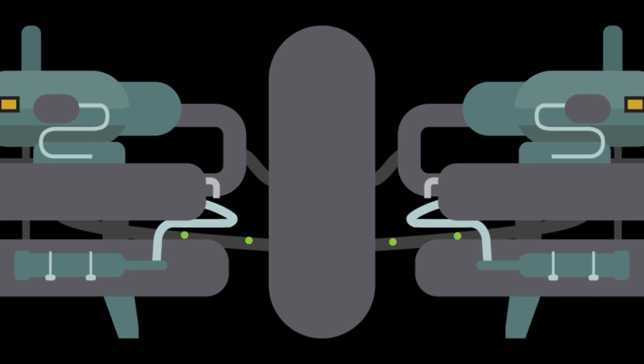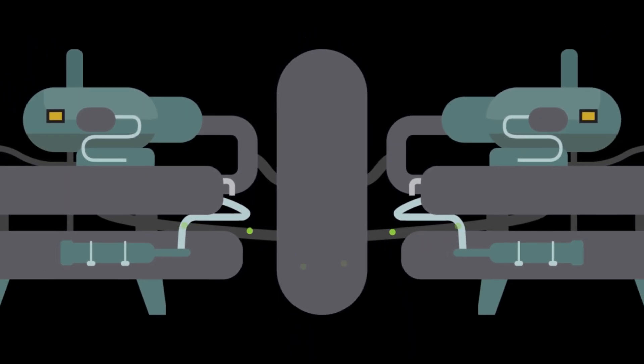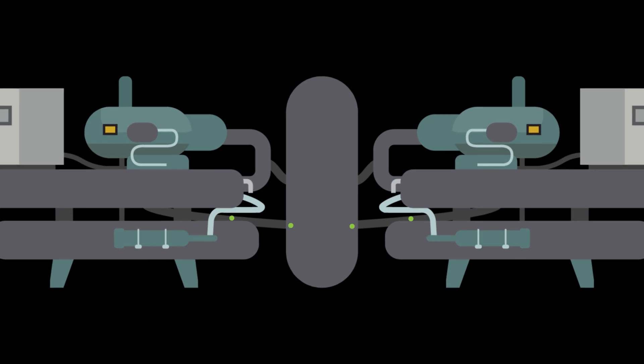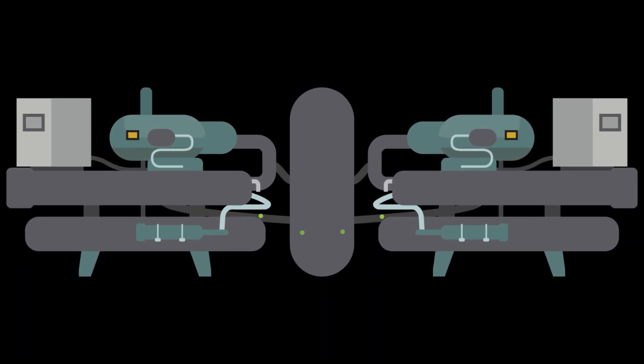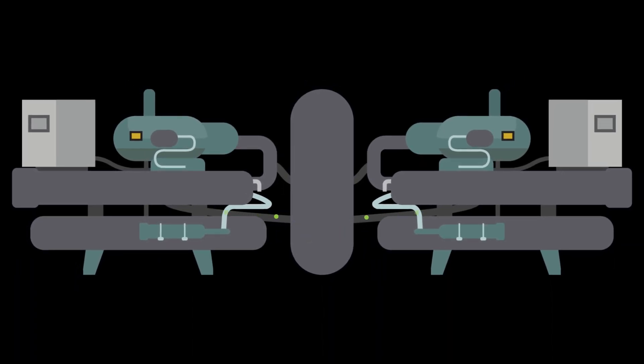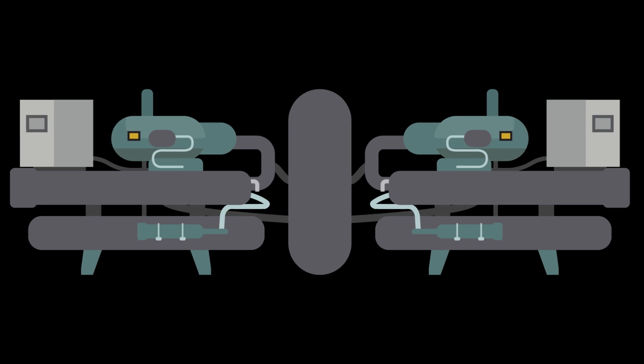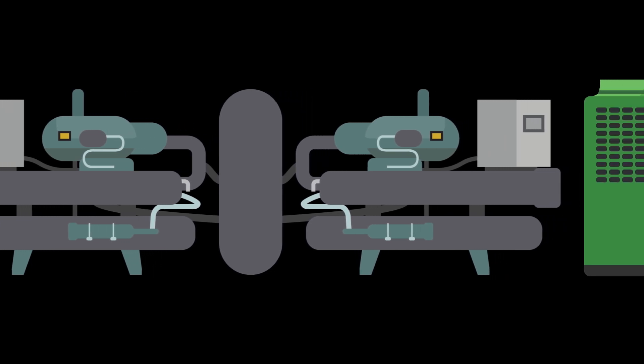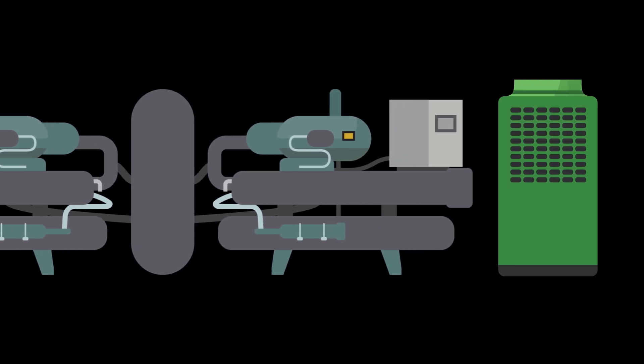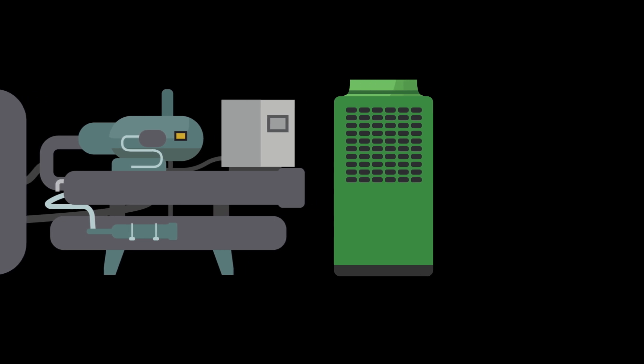In some specialized applications, large chilling and refrigeration systems have built-in refrigerant storage and recovery pumps to allow the refrigerant recovery to take place within the system that is being serviced. Systems of this type typically utilize a blend of programmable controllers, manually operated valves, and fixed piping. These components operate the built-in recovery pump, monitor critical measurements such as pressure and saturation temperature, and direct refrigerant and water around the system as needed. Systems of this design do not require auxiliary recovery specific tools and are often designed to accommodate fast refrigerant flow during these onboard recovery processes.